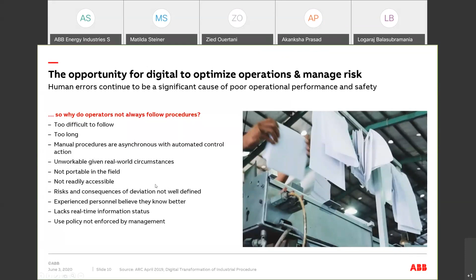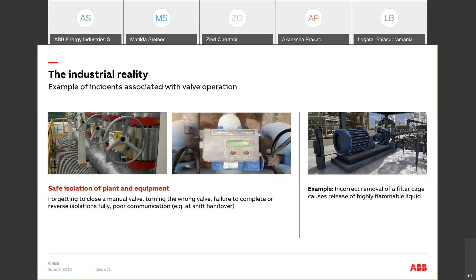Just to give some examples of things pointed out to us by our customers: typical incidents happen when we are acting on valves. There's a number of manual procedures that involve acting on a valve in a defined sequence, and here there is a potential for forgetting to close a valve, or turning the wrong one. You see on the picture here, they all look pretty much the same. A failure to complete the reverse isolation, poor communication, etc. And the impact of a small thing like acting on the wrong valve can, of course, be significant. If we don't safely isolate a pump, for instance, when we want to change a filter, it can be really hazardous for the people involved. It can also be smaller incidents, just having a material waste that I need to clean - it's a waste, it takes time, and it can impact production.